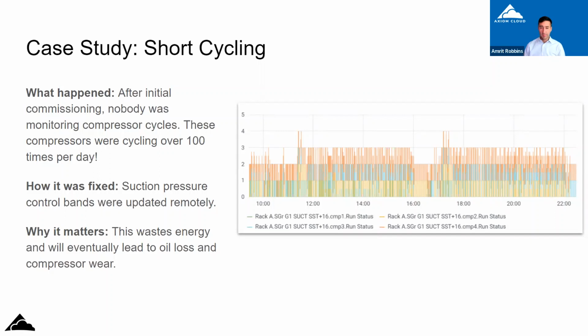And so by relaxing the suction pressure control bands a little bit, essentially like a dead band, the compressors can run a little bit longer before they end up cycling. And then changing some other programming on the rack enabled us to reduce the number of cycles per day from over 100 per day down to just a few. So this saves a lot on energy, but it also helps to avoid the oil getting flushed out of the compressor casing.